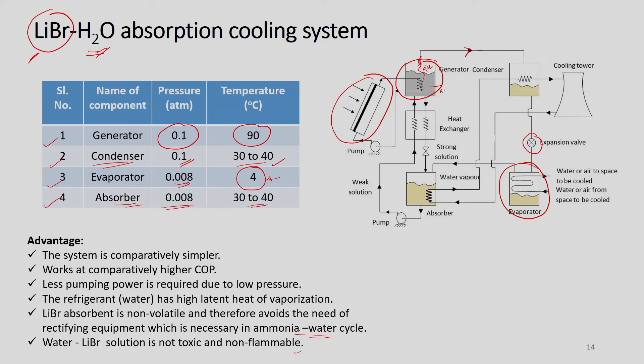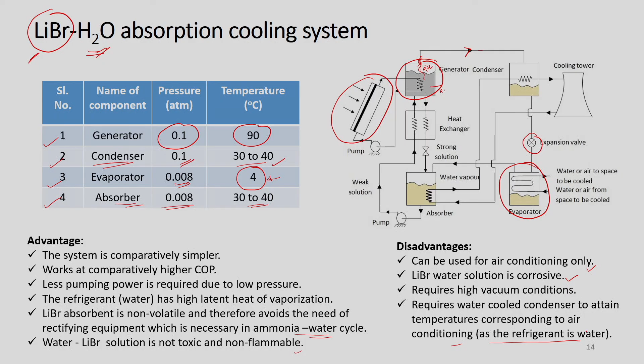Lithium bromide water solution is corrosive. That is very important. It also requires high vacuum conditions. Again, we need to invest in some kind of device or system for maintaining the vacuum, and it requires a water cooled condenser to attain the temperature corresponding to air conditioning. So, here the refrigerant is water.